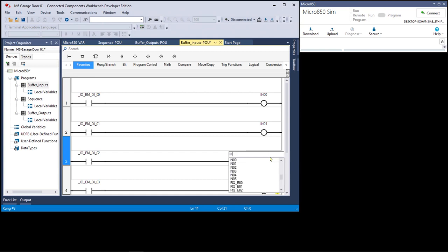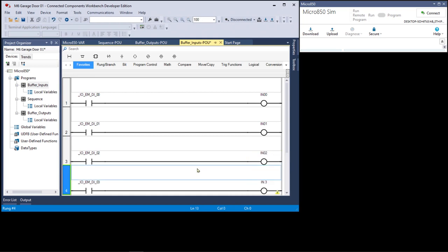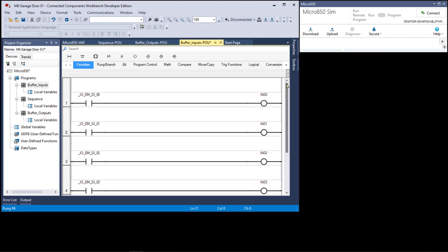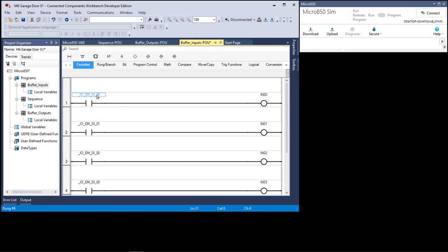And that takes care of my input buffers. My input buffer, I'm buffering the state of the screw terminal passed through the optical isolator to memory during the input update scan to these bits of memory. So these now become my inputs, not these.